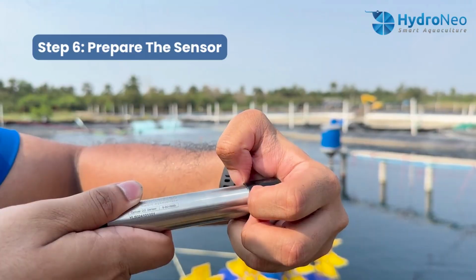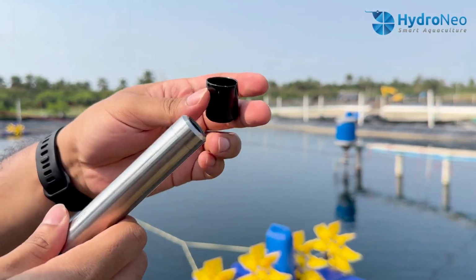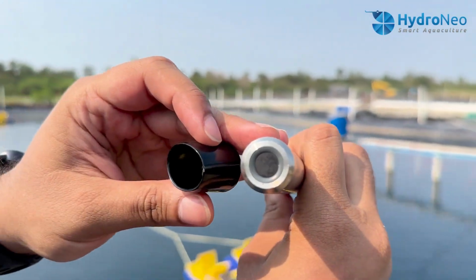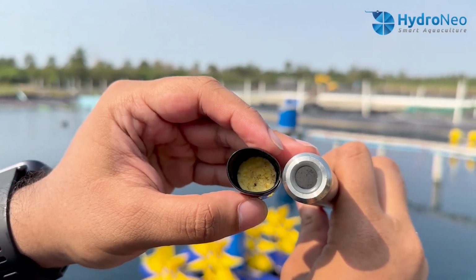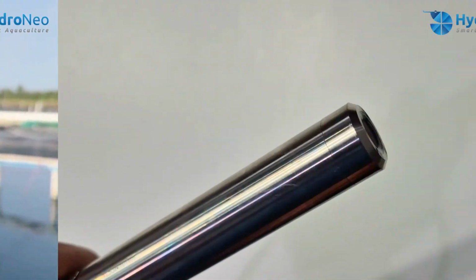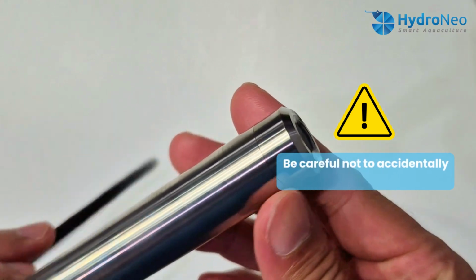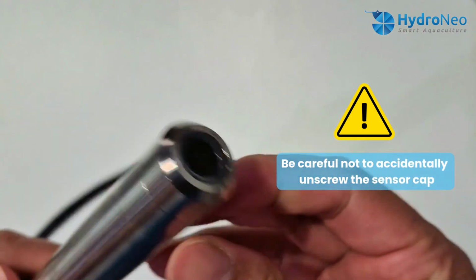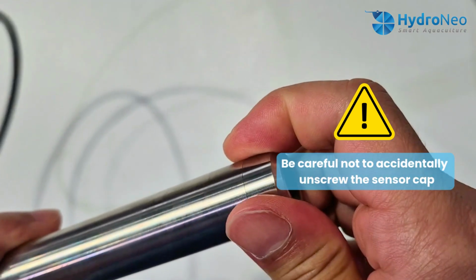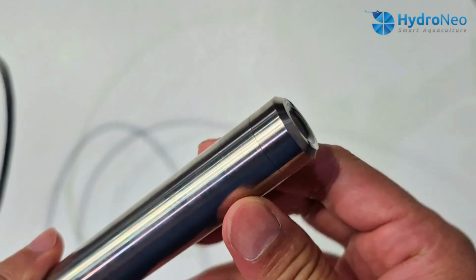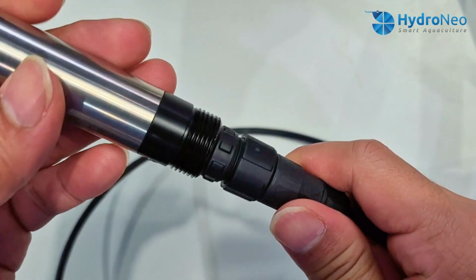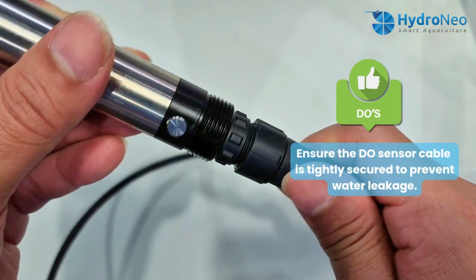Step 6. Prepare the sensor. Remove the black plastic cover from the sensor by gently pulling it off. Be careful not to accidentally unscrew the sensor cap, as this will lead to water leaks and sensor damage. Make sure it is still tightly screwed. Ensure the DO sensor cable is tightly secured to prevent water leakage.